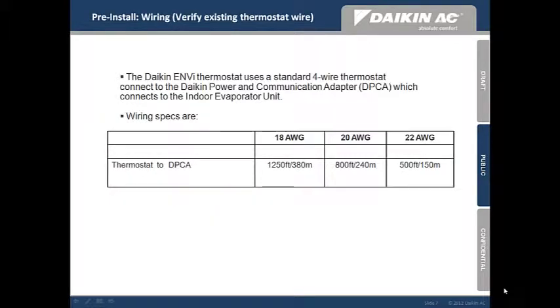Prior to the installation, the installer should verify the thermostat wiring in the wall. The Daikin ENVi thermostat uses standard 4-wire thermostat wire to connect the DPCA to the thermostat. From the chart, the larger the gauge wire, the greater the distance. For example, 18 gauge thermostat wire will give you up to 1,250 feet, whereas 22 gauge wire has a maximum of 500 feet.